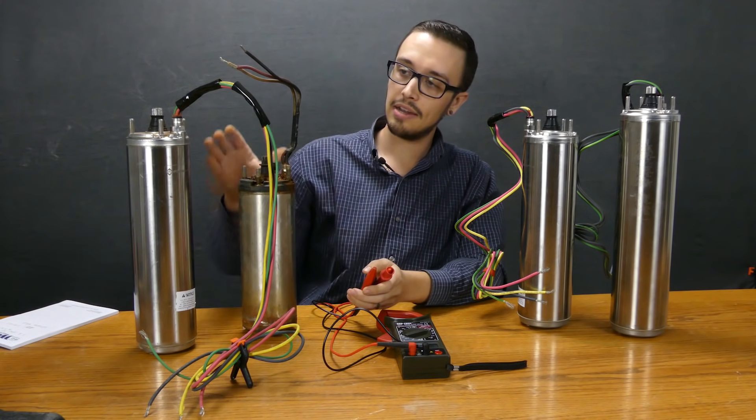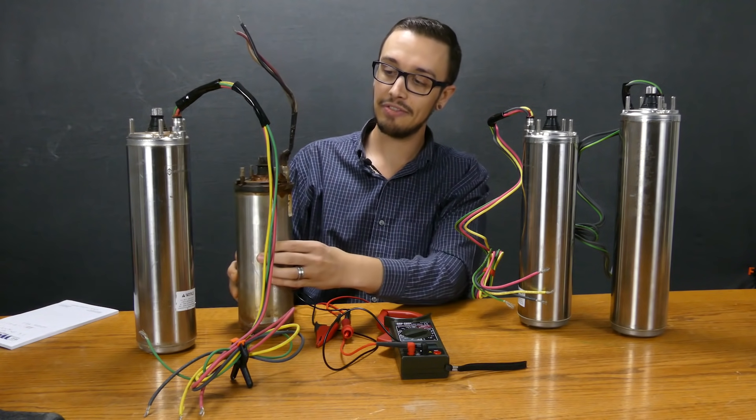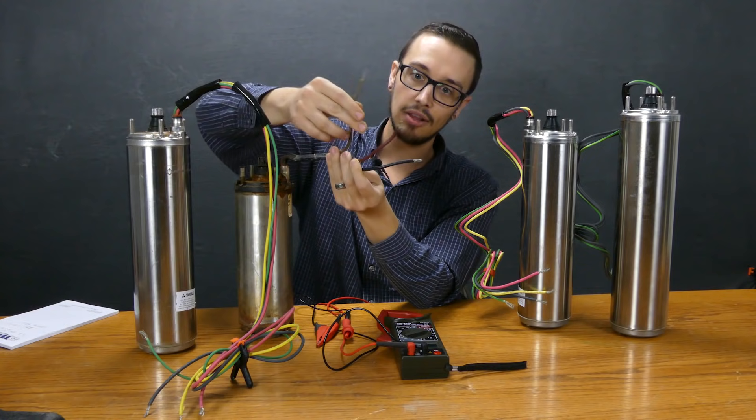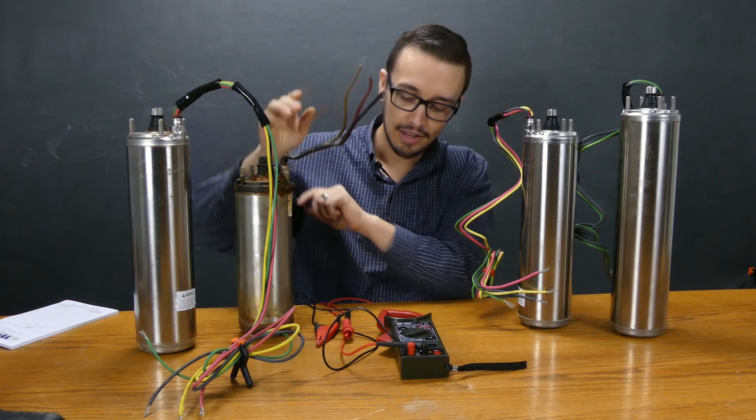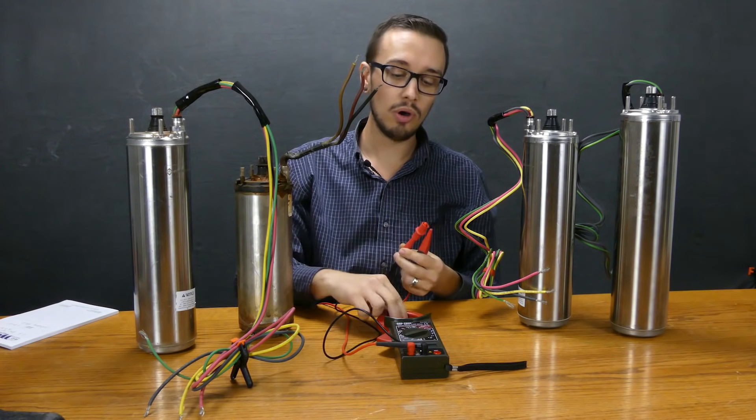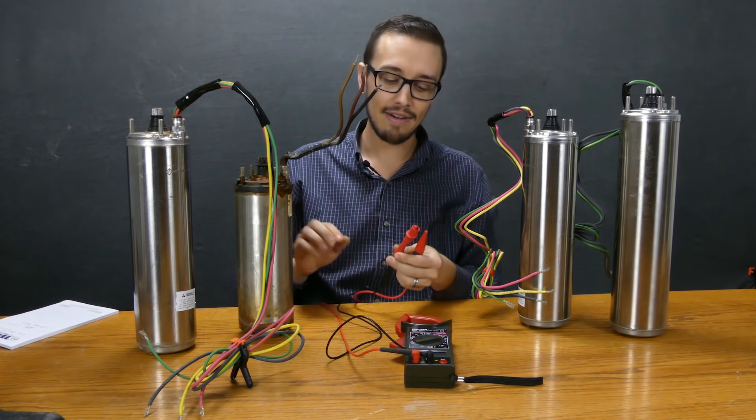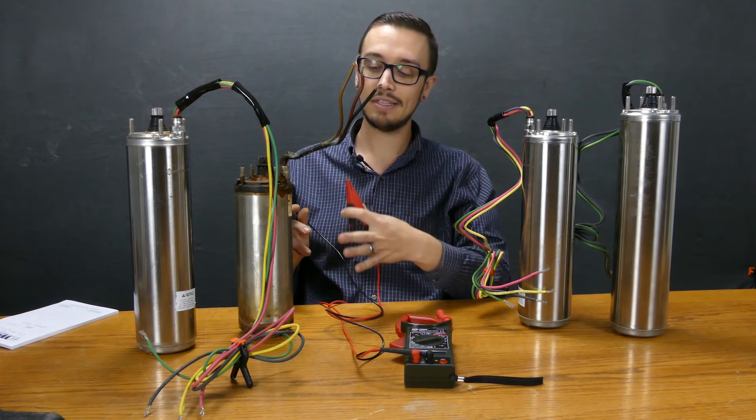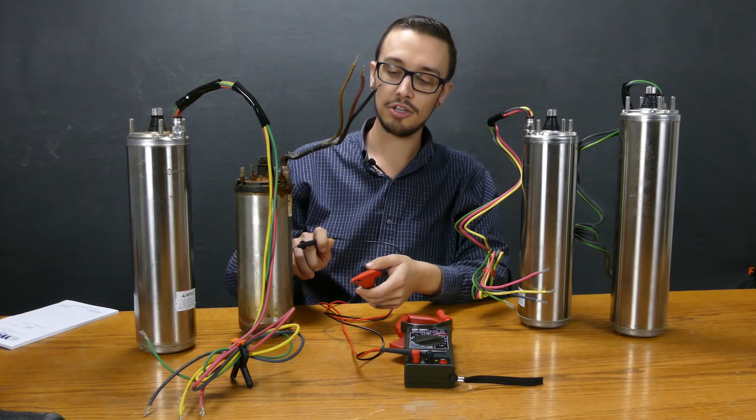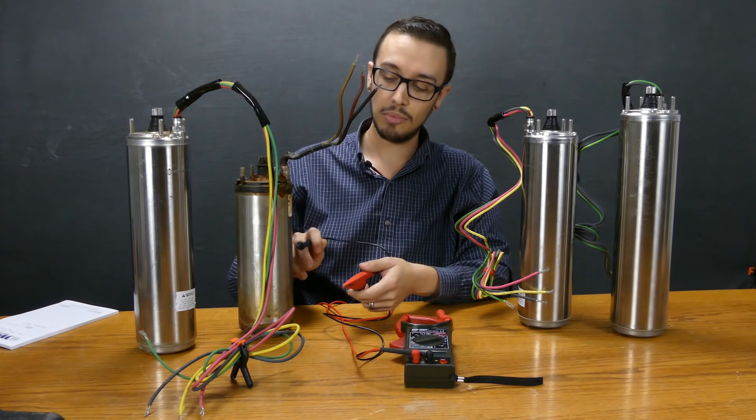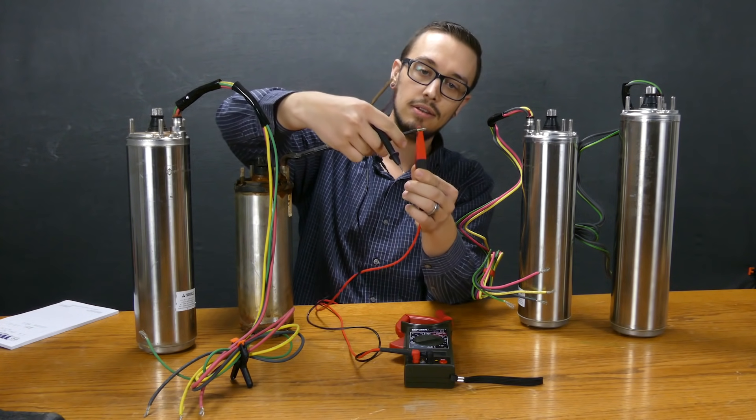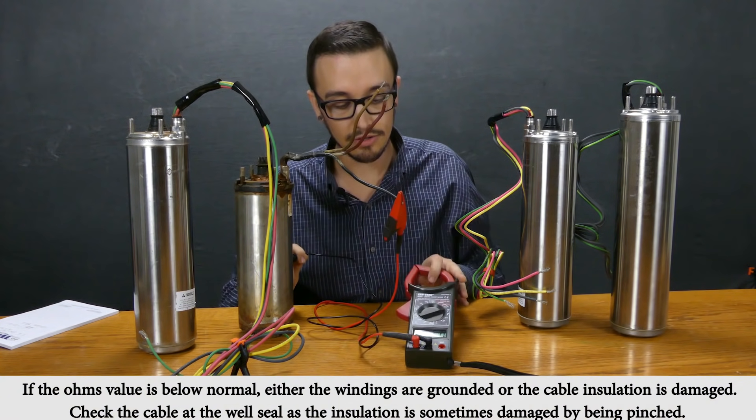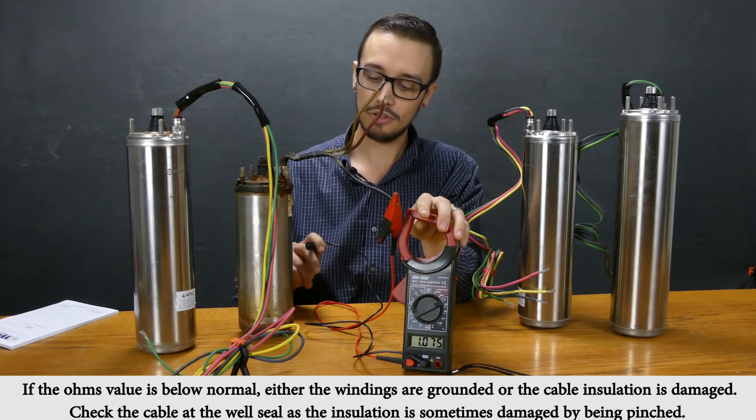Now I'll bring this motor over here. This is a pretty old motor - it doesn't actually even have a ground, it just has three wires: black, white or yellow assumably, and red. So the way that you test an old motor that doesn't have a ground is again you can use the well casing, or in this case since I have the motor right here I'll touch it to the side of the motor and then put the other clamp on this side here. You're going to see definitely not a one. So when I touch this to it...